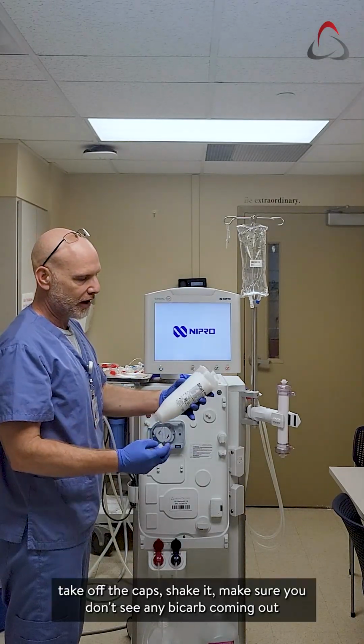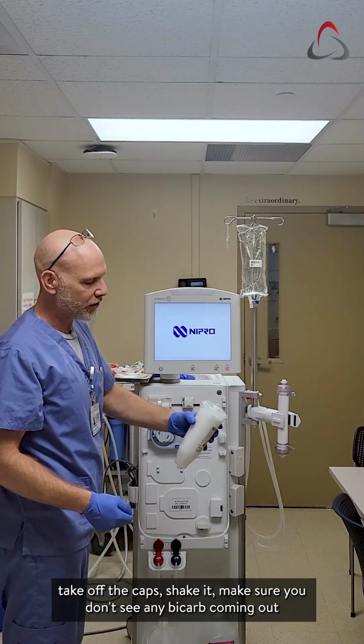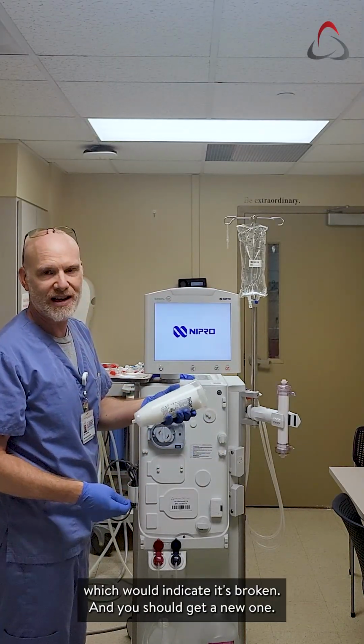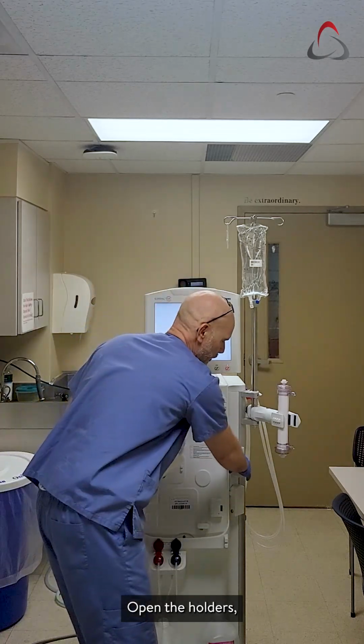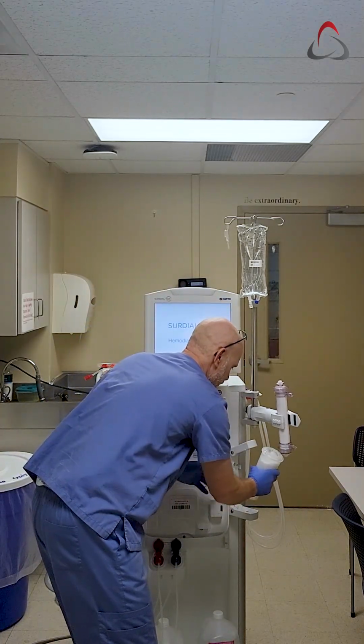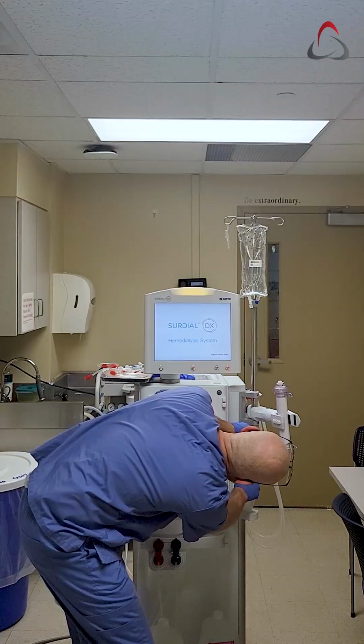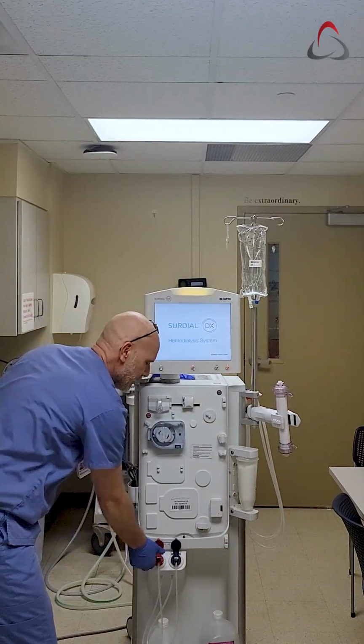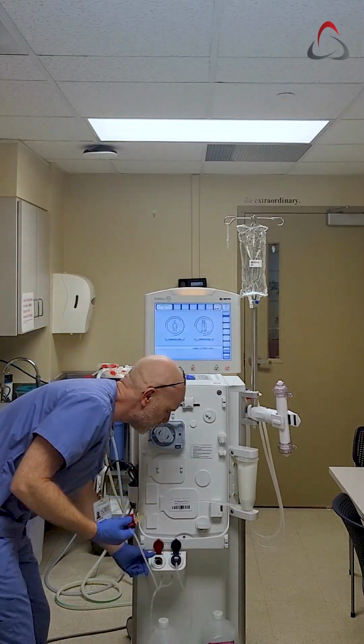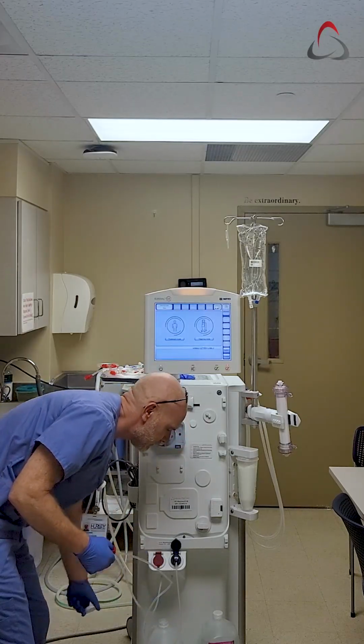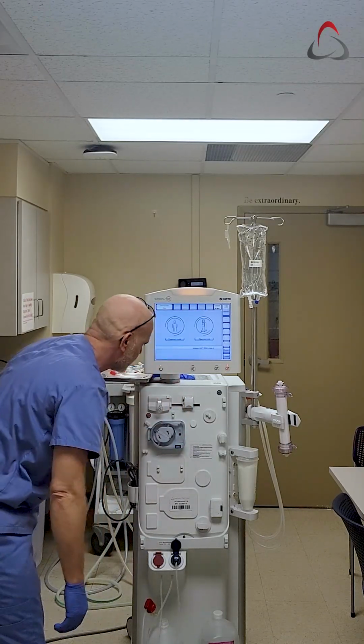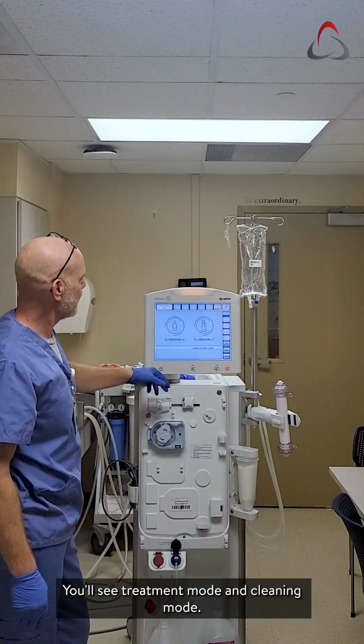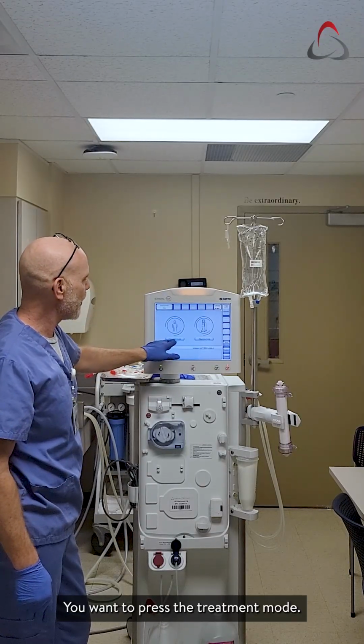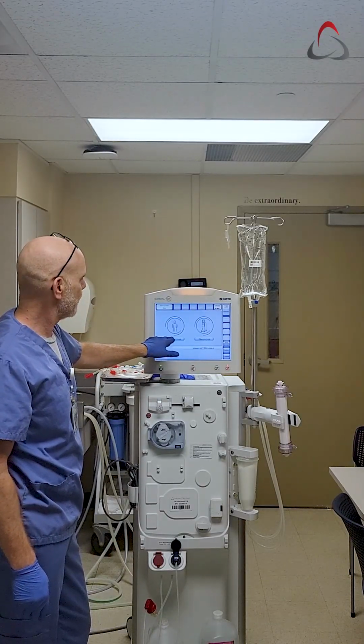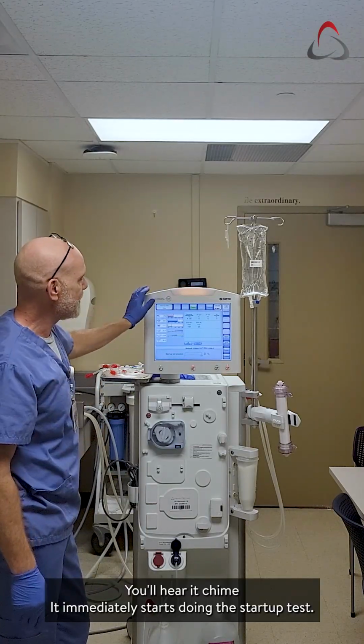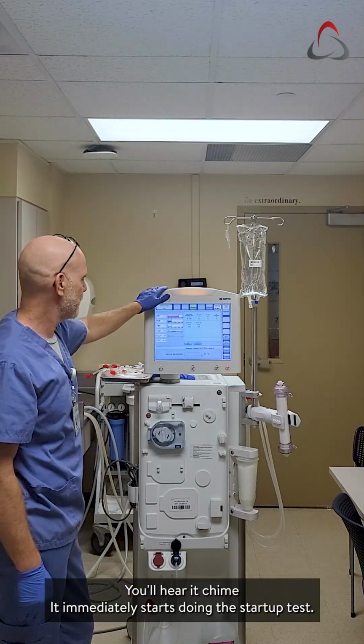Your bicarb, take off the caps, shake it, make sure you don't see any bicarb coming out, which would indicate it's broken and you should get a new one. Open the holders. Take the acid wand out, close the cover, put it in your acid jug. The startup screen comes up. You'll see treatment mode and cleaning mode. You want to press the treatment mode. You'll hear it chime. It immediately starts doing the startup test.